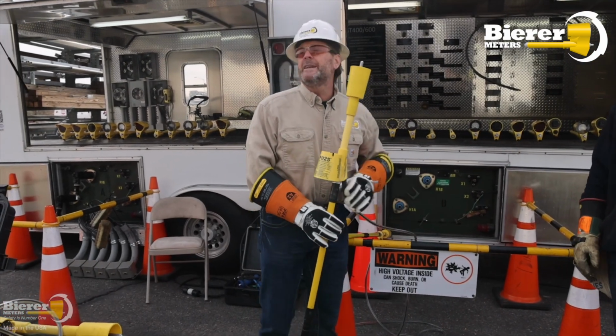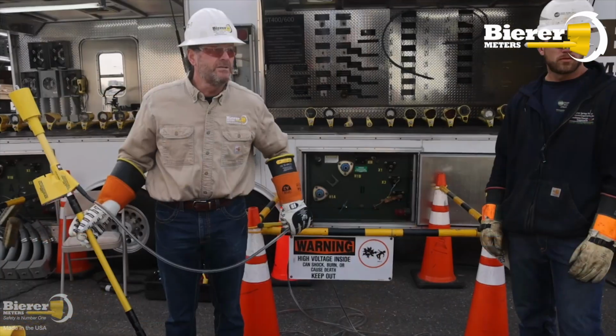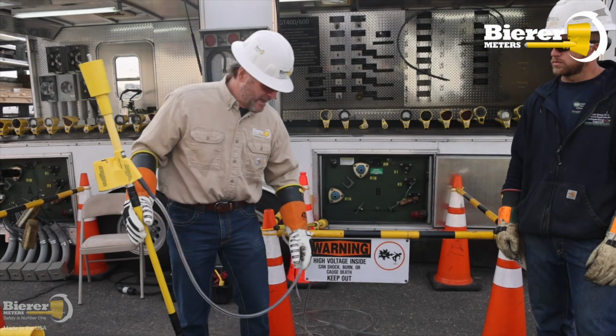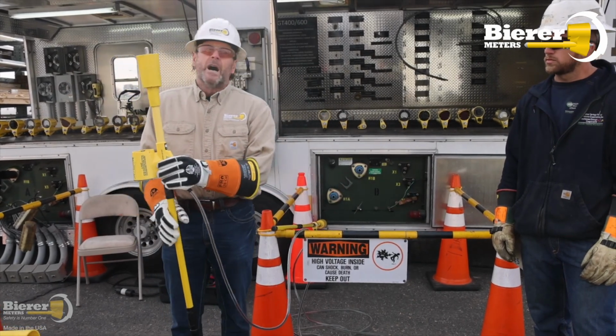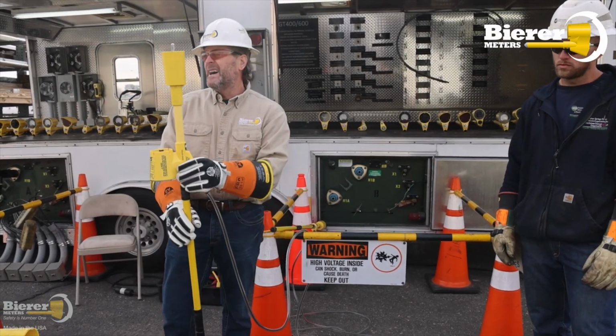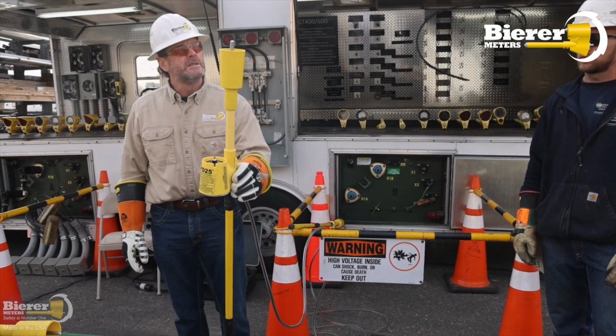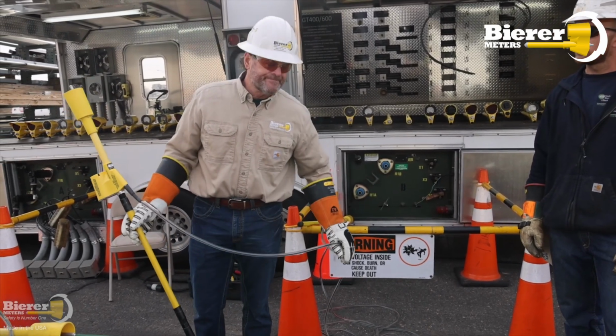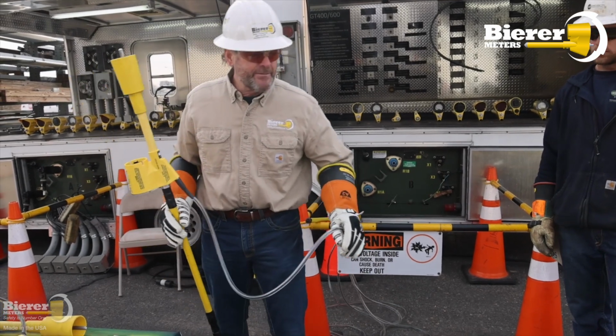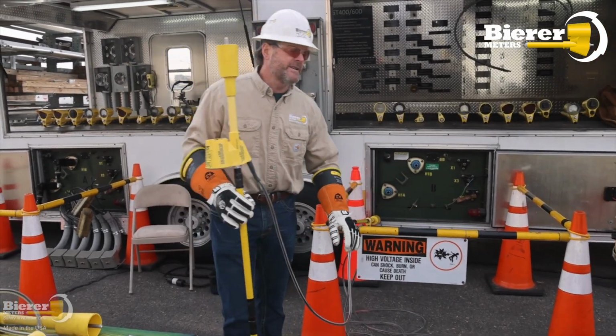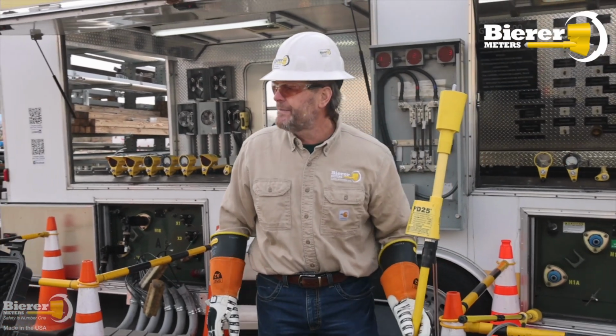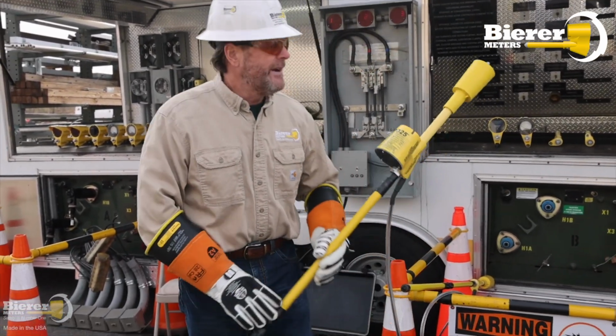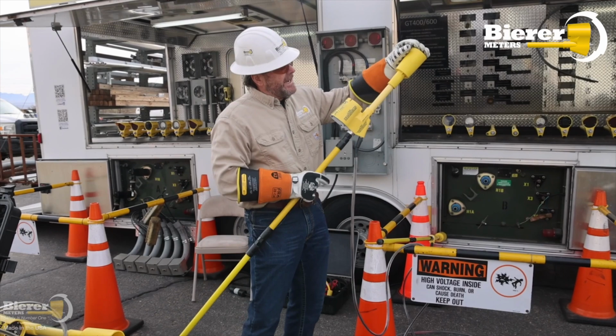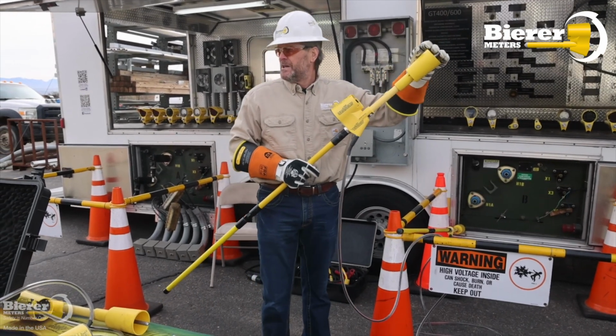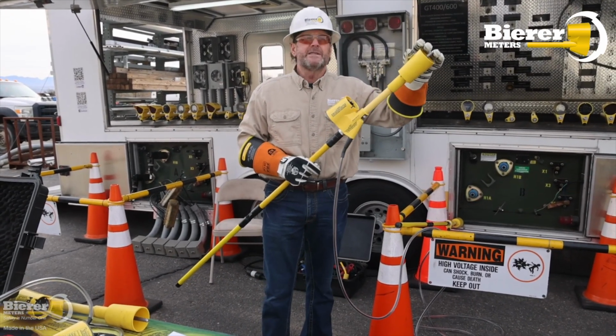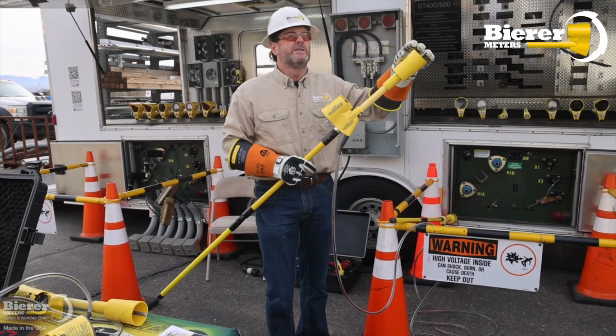Do you all do any wireless phasing? You do? Okay, so let's talk about wireless phasing. But first, before I do that, I got a call from a utility, I won't say their name. And the utility said, hey, we had an arc flash, and it was pretty serious. We were using your PD25, and we were in a substation, and we made contact with a hot bus, and we had an arc flash. Oh really? Okay, well they sent us the picture, and check it out.